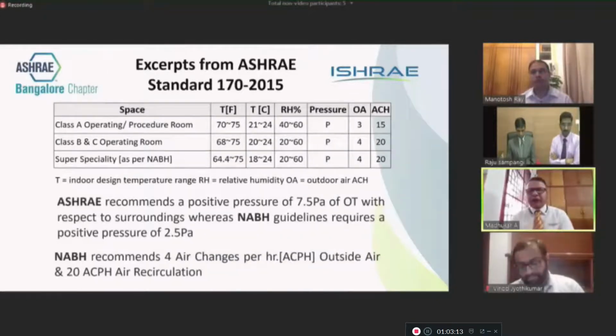Coming back to the conditions recommended by NABH with respect to positive pressure and negative pressure, the minimum positive pressure advised by ISHRAE is about 2.5 pascals, whereas NABH recommends about 4 air changes per hour and 20 air changes of recirculated air.